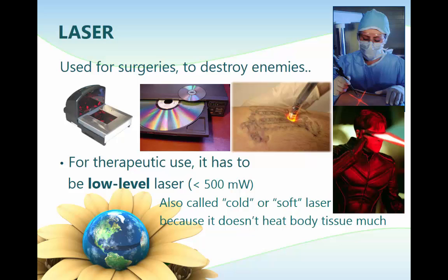Lasers, LEDs, and superluminous diodes used in rehabilitation are very different from those used in other areas of medicine. The biggest difference is power — the maximum output for rehabilitation devices is less than 500 milliwatts. These low-level lasers are also referred to as cold lasers or soft lasers because they do not heat body tissues. Other laser applications in daily life include laser discs, supermarket scanning, tattoo removal, LASIK surgery, and many other examples.